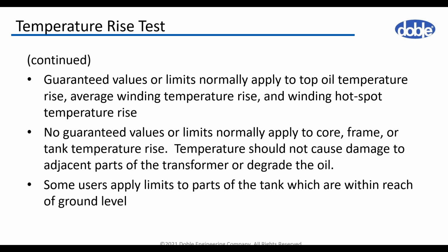The limits for top oil temperature rise, mean winding rise, and winding hotspot are guaranteed values. There is no limit to other special parts like core or tank temperature rise, but the heat generated should not cause damages to the unit or degrade the oil. Some users apply limits for parts which are accessible from ground level for obvious reasons.